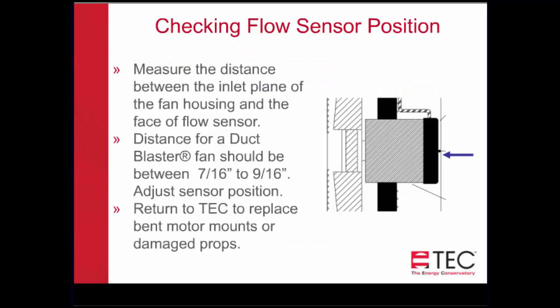The same is done for a Duct Blaster fan, but that one is about a 1/2 inch for the location from the edge of the fan housing to the motor, and it's measured against the motor itself. We don't talk about the flow sensor, because the flow sensor is fixed and screwed to the back of the motor, so you can't adjust the flow sensor back and forth. It's strictly a situation with the motor, so we just want to make sure that it's tight. Because the motor of the Duct Blaster fan is lighter, it doesn't have as much inertial force when it gets dropped like a blower door fan. So that's the quick and easy of how to check the flow sensor position and how to check the leak on the Duct Blaster fan.